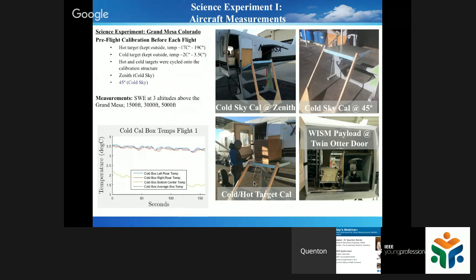In the right-hand corner, it's at 45 degrees. Remember, the instrument is pointing 45 degrees. Going to the left, one block in the upper left-hand corner, we can see that we can point zenith just by tilting our calibrator up. And at cosmic background, I think at Ku band it's around 9 Kelvin or something, and at Ka band it's 16 Kelvin. Depending on the day, I might have those two switched around. But we also take measurements with a cold and a hot black body. In the bottom left-hand corner, that box has absorber inside of it, and we're looking out of the door with the radome in the front. Remember, I characterized the radome. And once again, we're taking measurements at 1,500 feet, 3,000 feet, and 5,000 feet. I think I mentioned meters before.